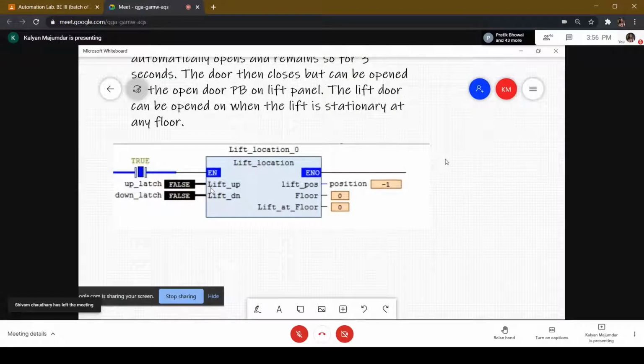The further outputs of this model are the outputs of the 4 position sensors, indicating whether the lift is presently at ground floor, first floor, second floor, or third floor - an important input to your controller. Plus, there's 'lift at floor', a number indicating what is displayed: 0 if at ground floor, 1 if displayed at floor 1, and so on.